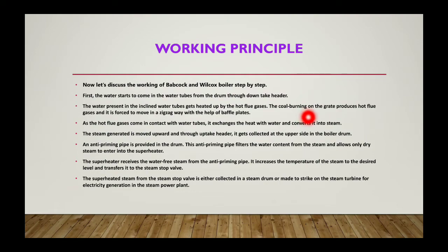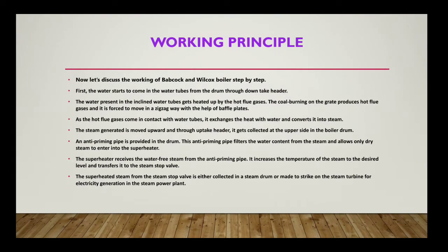burning on the grate produces hot flue gases, and they are forced to move in a zigzag way with the help of the baffle plates. So these plates are used to supply the flue gas surrounding the water tube in a zigzag way.